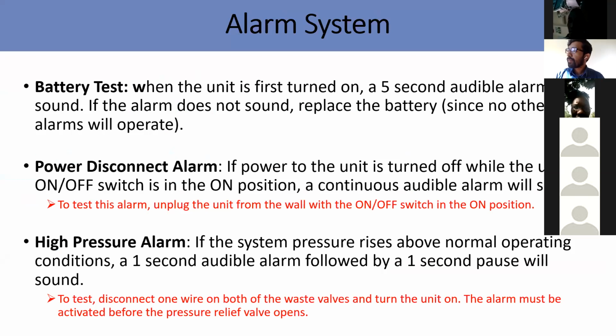Working principle of oxygen concentrator: basically, when you talk about oxygen concentrator, you need to know the alarm system. Most of the alarm systems in oxygen concentrators will notify you of power disconnect, high pressure, and some even have an oxygen purity indication, depending on the brand and model.